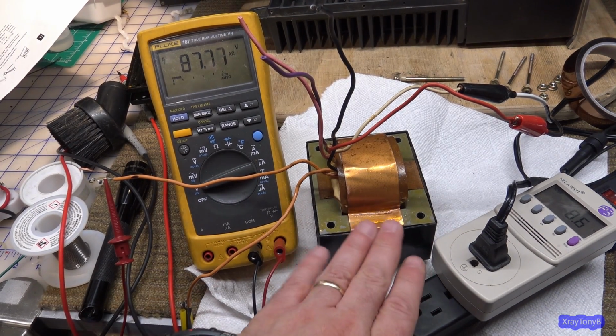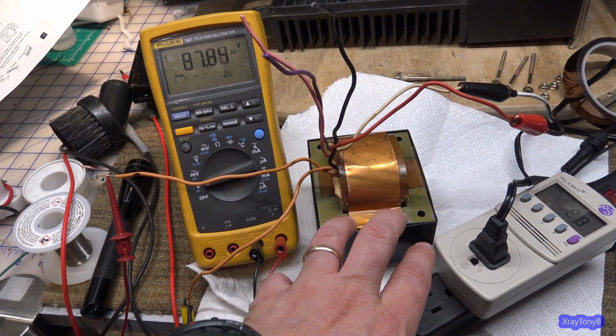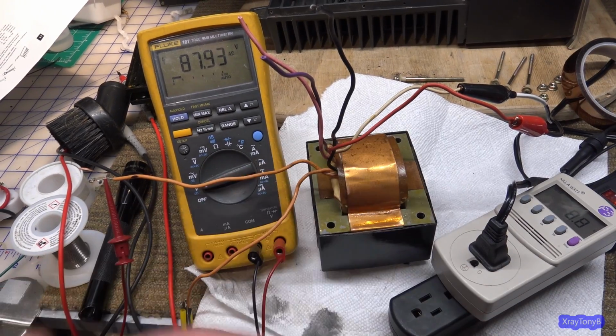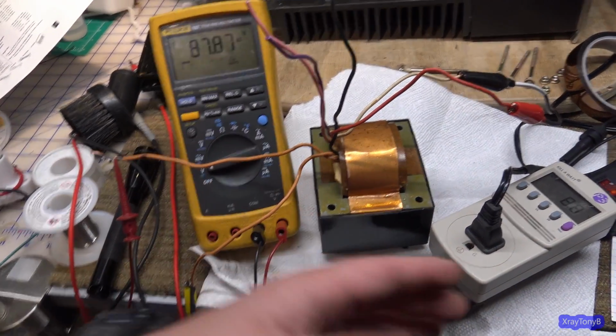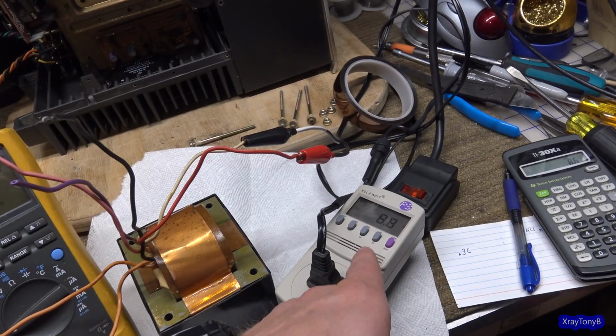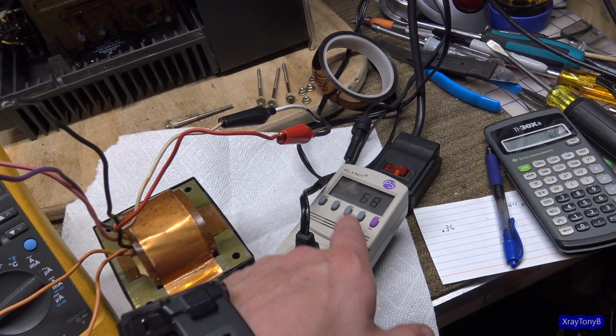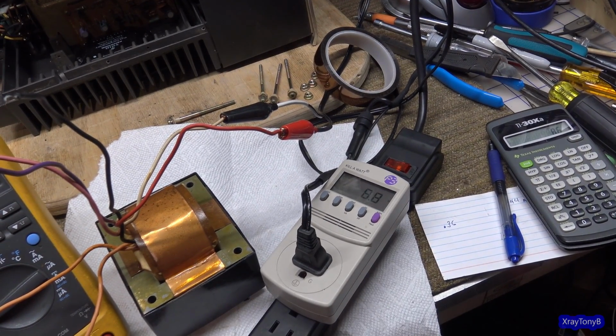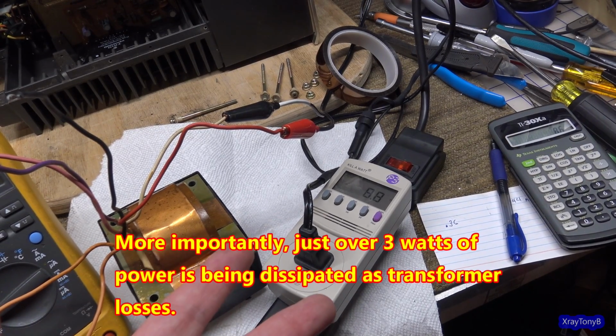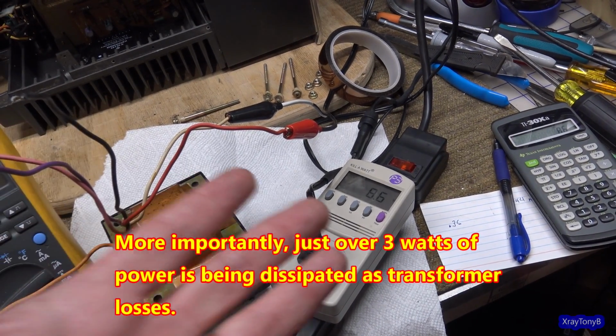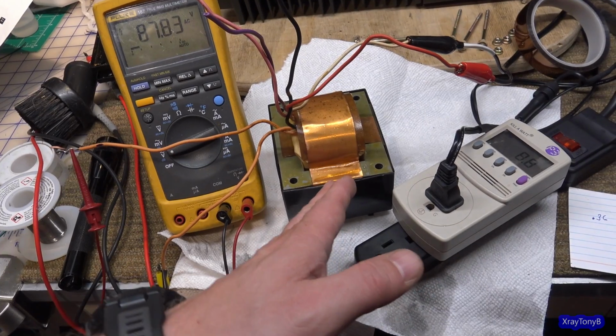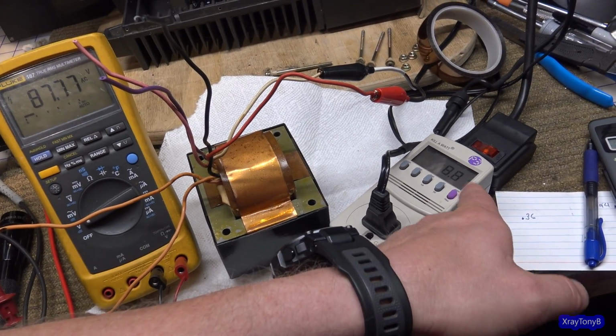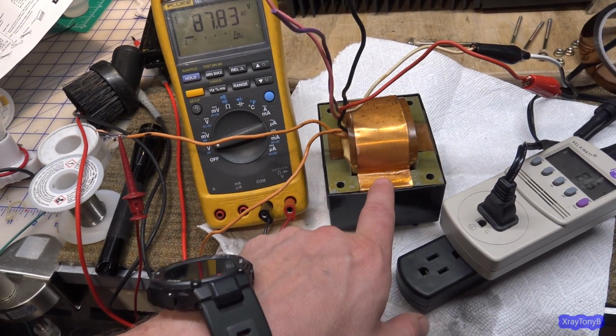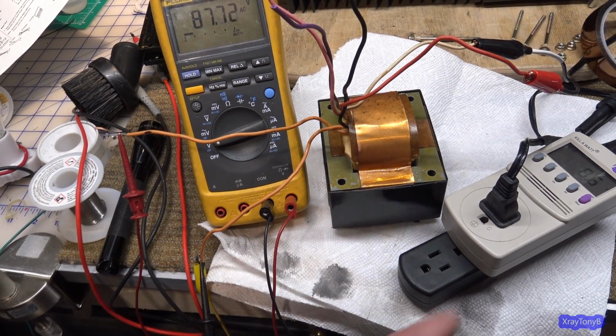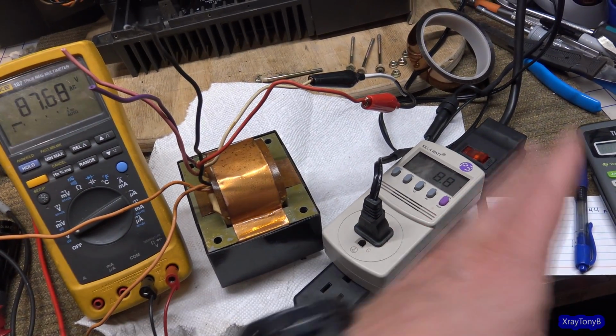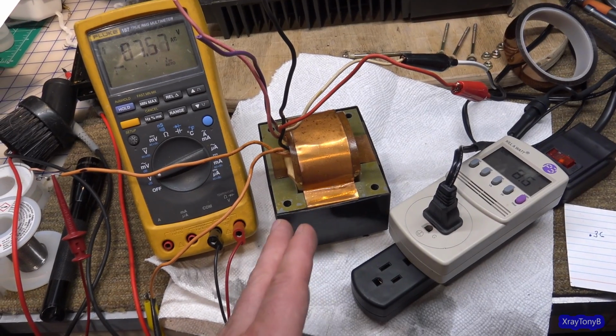Because if the transformer core shorts out like that, those eddy currents are going to influence this. What's going to happen is you're already using 8.8 VA of power that you're dissipating in this transformer, and most of that is going to be dissipated as heat. That's actually relatively low for a transformer of this size.